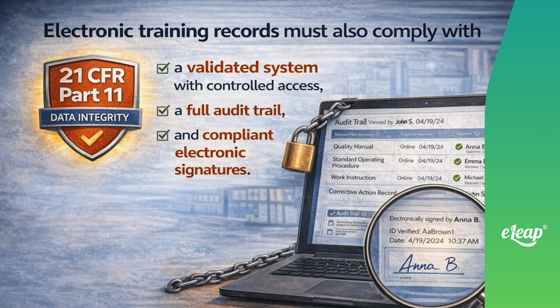Electronic training records must also comply with 21 CFR Part 11: a validated system with controlled access, a full audit trail, and compliant electronic signatures. A spreadsheet on a shared drive does not meet this requirement.